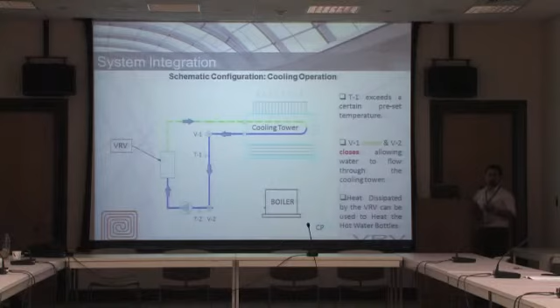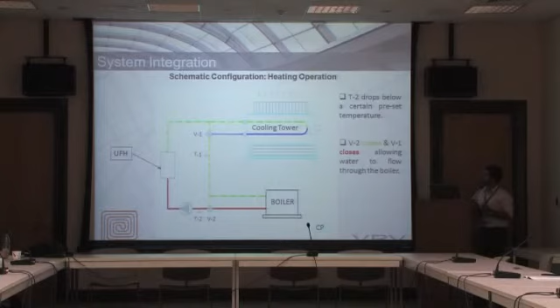During cooling operation, T1 are the temperature sensors and V are the motorized three-way valves. When T1 exceeds a certain preset temperature, for example 30 degrees, V1 will open and V2 will close, and the water will circulate through the cooling tower and condition the VRV. Heat dissipated by the VRV can be easily used to heat the hot water bottles. In the heating operation mode, the underfloor heating requires hot water temperature. T2 will drop below a certain preset temperature, let's say 45 degrees. V1 will close and V2 will open, and the water will be circulated through the boiler.